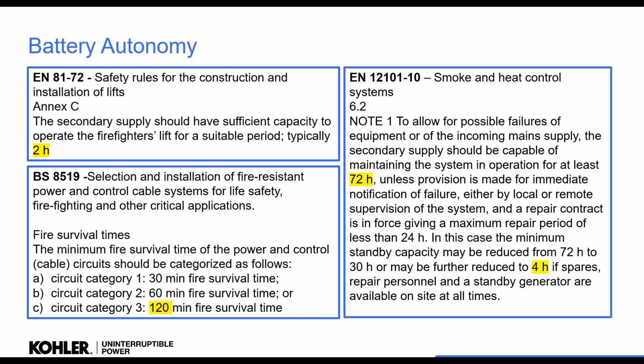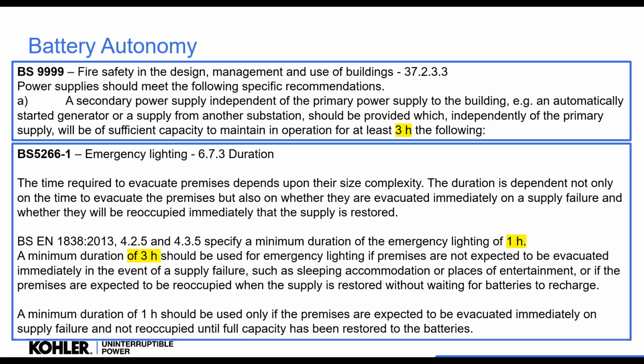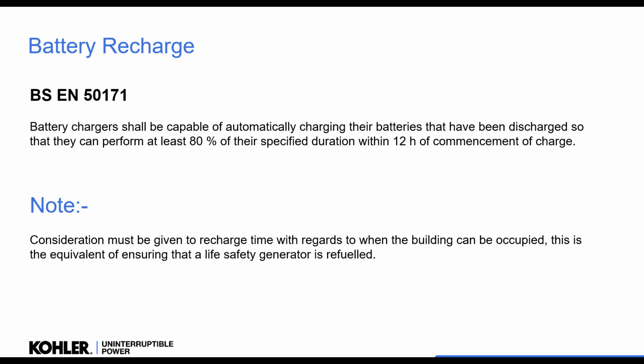Again, it talks about generators being available in fuel tanks and things like that. Okay, again, hasn't caught up. So you have to make that decision of how long it needs to be. All right. Double nine talks about a sufficient capacity to maintain an operation for at least 3 hours. Okay. Then you have the emergency lighting, which is 1 hour or 3 hour, depending on if you're going to evacuate the building or not. Okay. Now that's very important to talk about this. You know, are we going to evacuate a building, or when can we go back in? Okay.